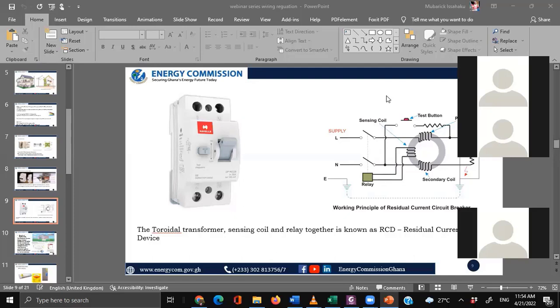So in electricals, there is something we call a return current. Once your current comes to the facility, the current doesn't stay there. It has to return to the supplier, the supplier's transformer. So the neutral cable is what returns the current back to the supply transformer. So what this RCD does is compare the currents here. And if the live current is flowing through the RCD to your appliance, it creates something we call an electromagnetic field. And this electromagnetic field is compared to the one coming out from the neutral side through the secondary coil. So another electromagnetic field is being created.